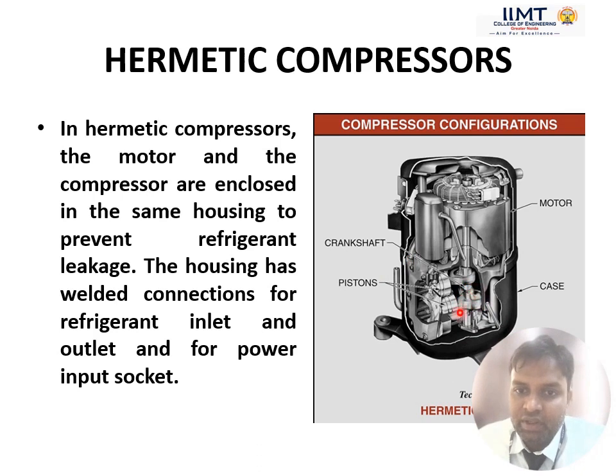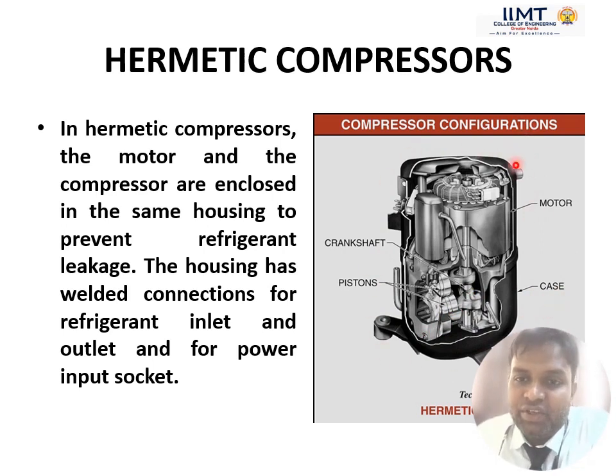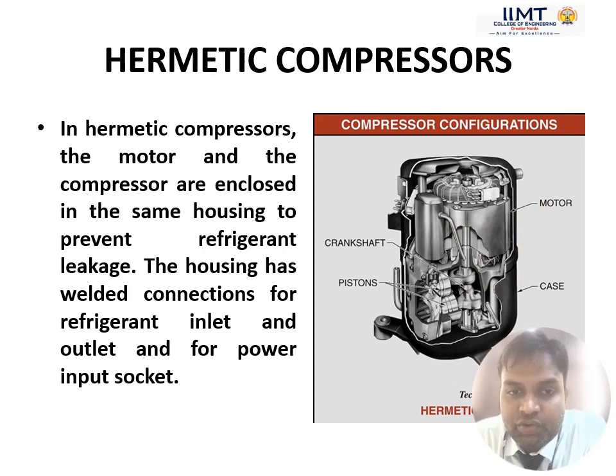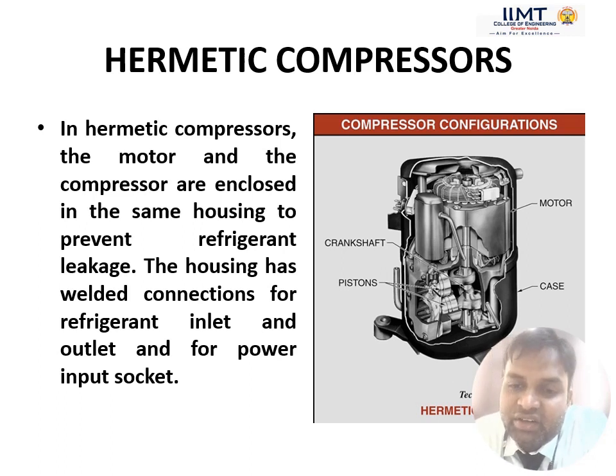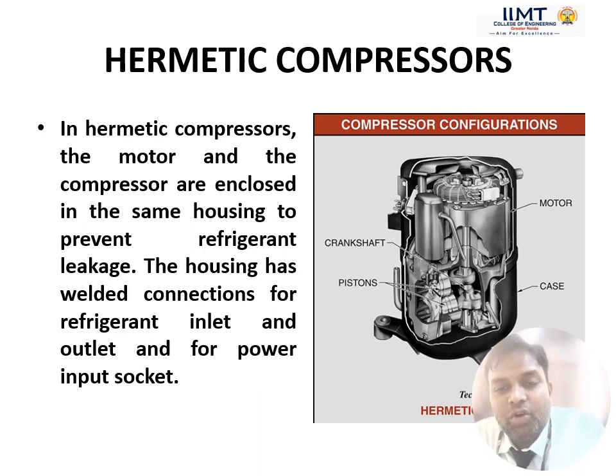The hermetical compressor has a crankshaft, piston, and crank, all enclosed in a sealed steel cover. Inside, the motor rotates the reciprocating compressor which compresses the refrigerant. The motor shaft and compressor shaft are connected using the same shaft. Vibration and noise are less, which is why it can be used in homes for air conditioning and refrigerators. In contrast, an open belt-type compressor produces a lot of noise, like the compressor seen at roadside puncture repair shops.